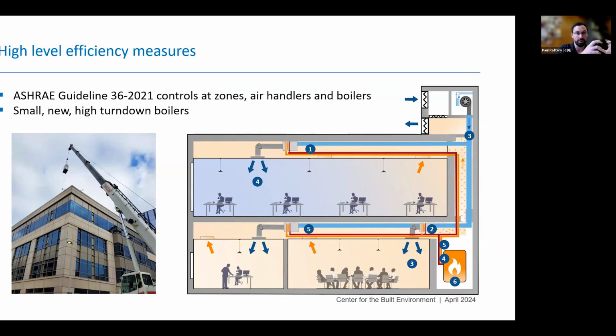We worked from the individual zone level all the way up to the air handlers and the boiler plant. That part is key because all of those savings don't just add together, they multiply together. You save a few percent at each zone, and that makes all of the supply temperature and other types of resets operate more efficiently.